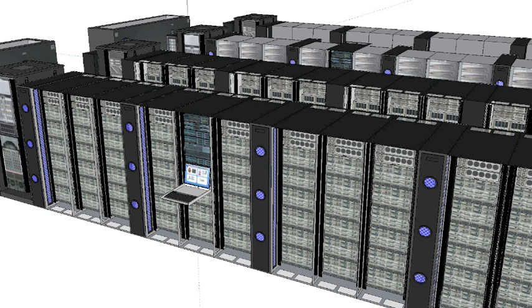So in this case, we're showing 6 5108 UCS chassis. That will draw about 21 kilowatt nominal cooling requirement per rack. And you can easily cool that with the in-row cooling design. These units can cool up to 30 kilowatt per rack, even higher in some situations. So you can be space efficient, cooling efficient, and power efficient all at the same time.